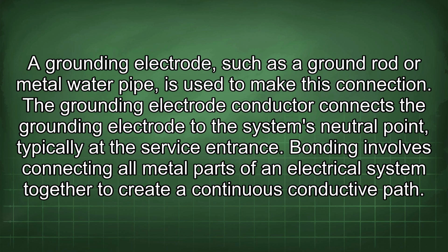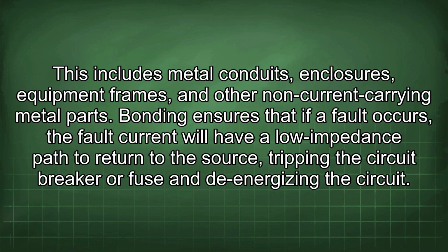Bonding involves connecting all metal parts of an electrical system together to create a continuous conductive path. This includes metal conduits, enclosures, equipment frames, and other non-current carrying metal parts. Bonding ensures that if a fault occurs, the fault current will have a low impedance path to return to the source, tripping the circuit breaker or fuse and de-energizing the circuit.